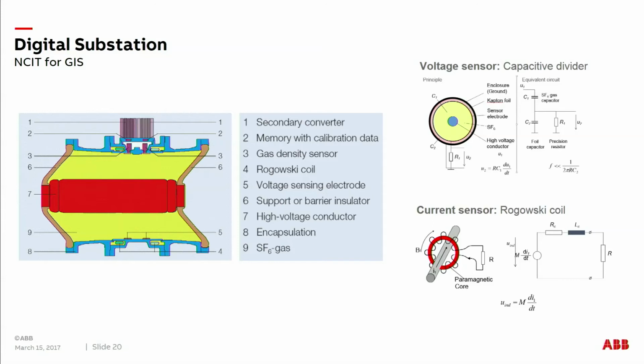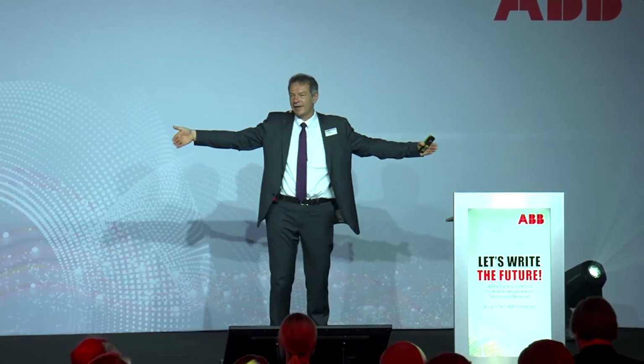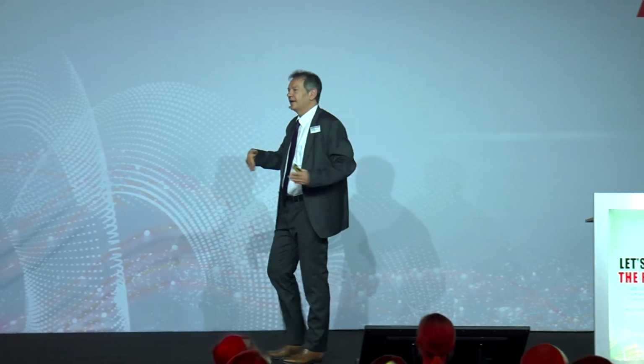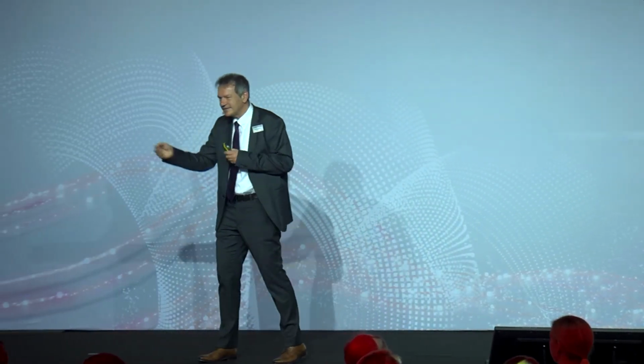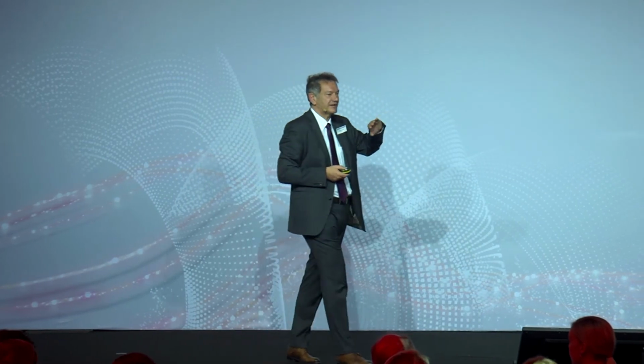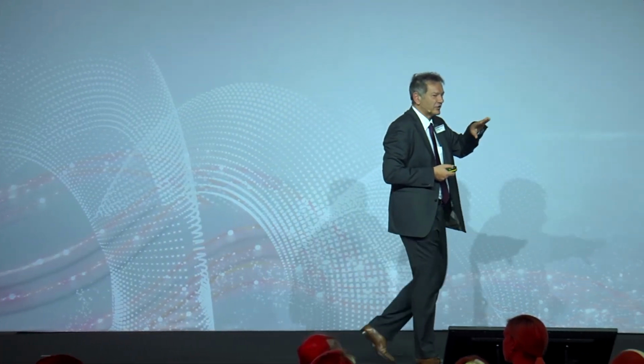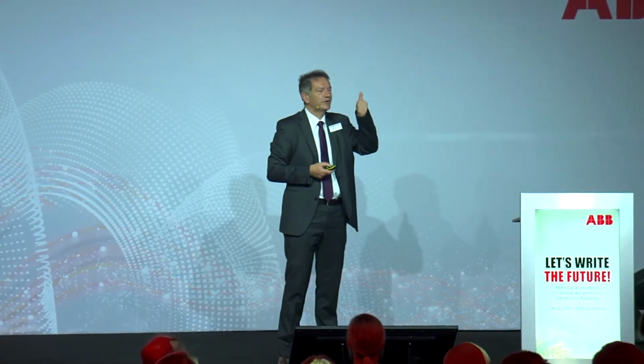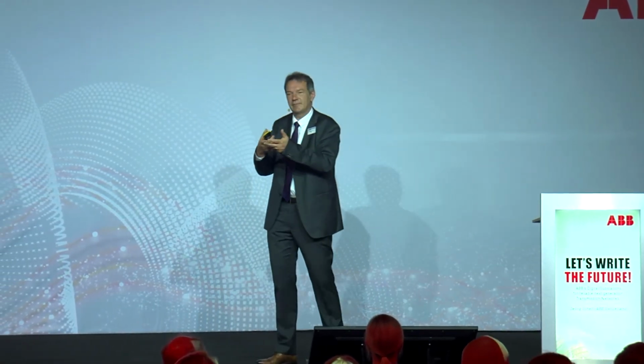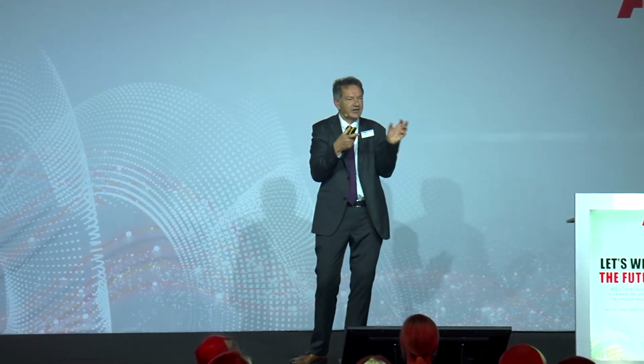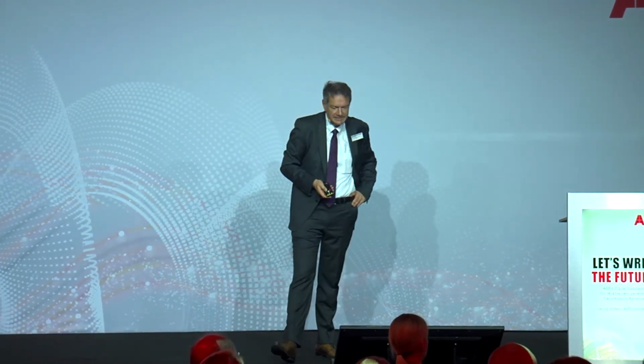Extremely precise. Today, conventional current transformers, as specialists know, have a nonlinear characteristic, they have a hysteresis, and that means that for each type of measurement you need a completely different core. So at the end of the day, measuring current in a conventional substation needs a lot of cores, a lot of engineering, and a lot of wires. With sensors, they are perfectly linear because they have no core. So there is no saturation. Therefore they are linear, and therefore you need only one sensor for control, protection, and metering. That completely changes the way you can engineer substations.